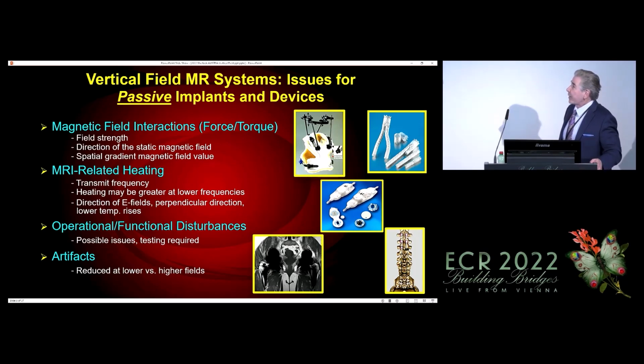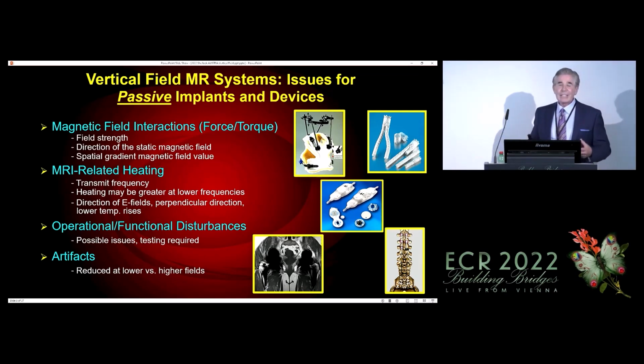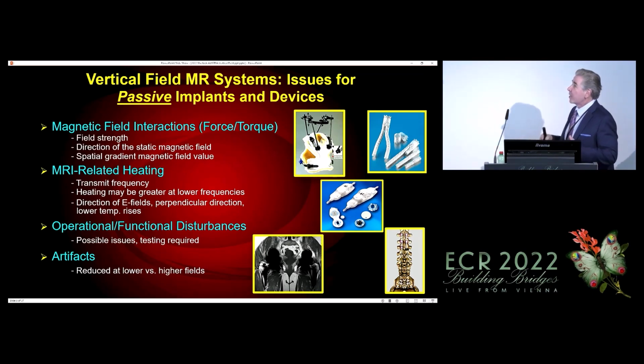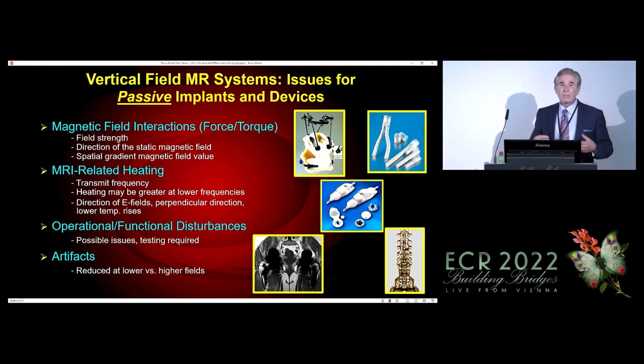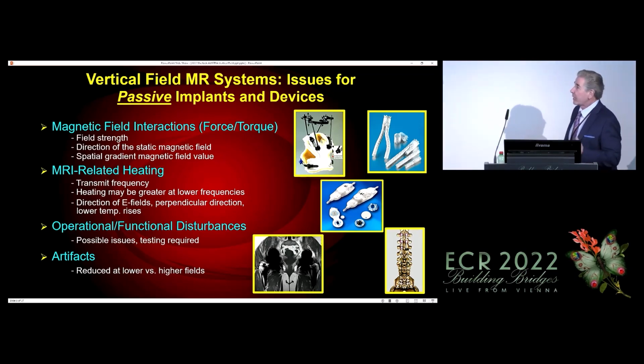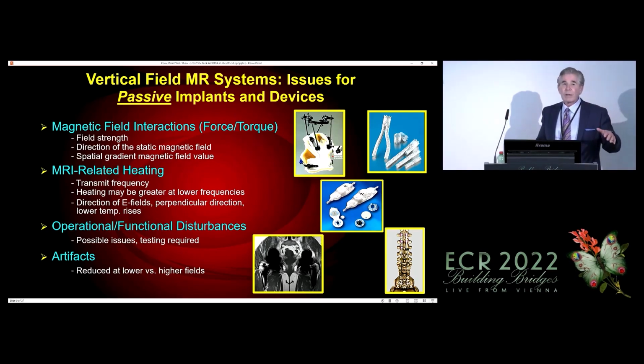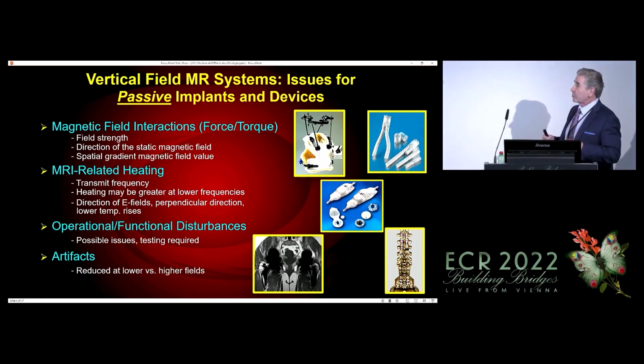The next factor to recognize, and sometimes it's not given enough attention, is MRI-related heating. Anything that's a conductor, so essentially metal, and there are other materials that also have conductive qualities, can potentially heat and cause a serious injury in a patient. And that's happened in many instances with regard to both passive and active implants. When we're looking at MRI-related heating, we need to understand what the transmit frequency is. And the higher the frequency is, the shorter the length of an implant that would inherently result in what's known as the antenna effect or a resonant effect, where you can have substantial heating resulting in a burn in a patient.